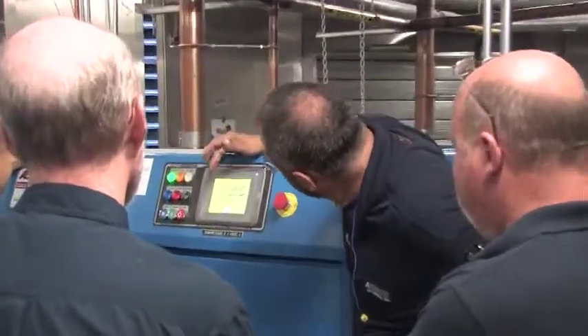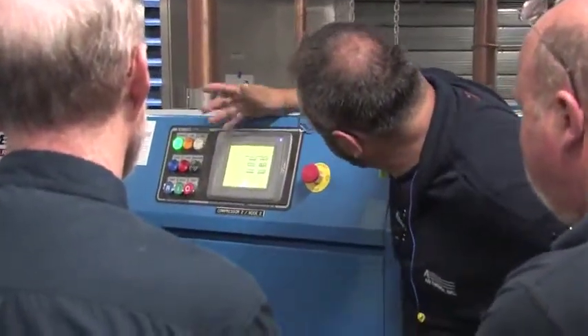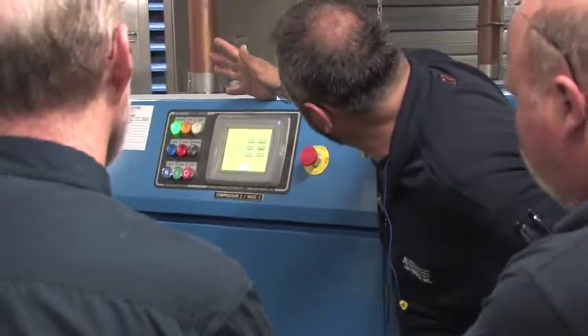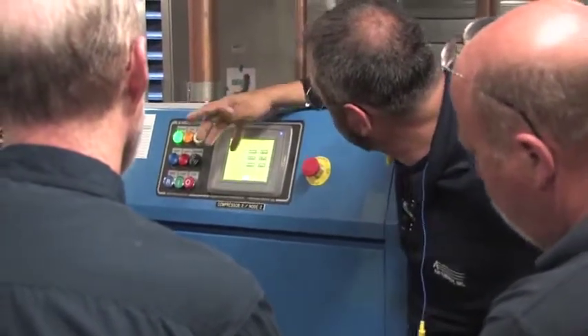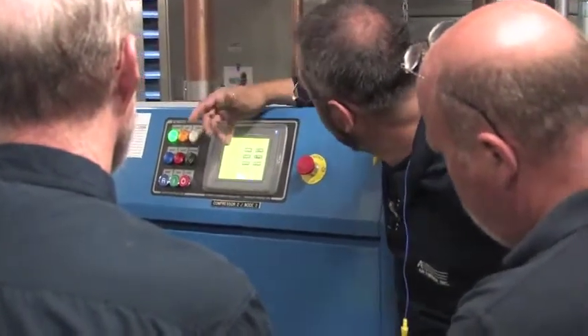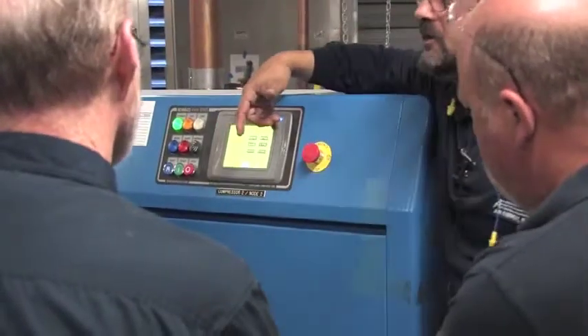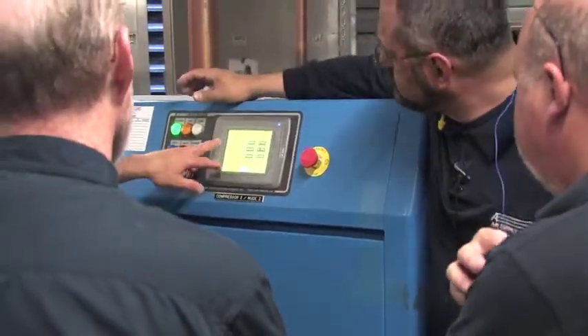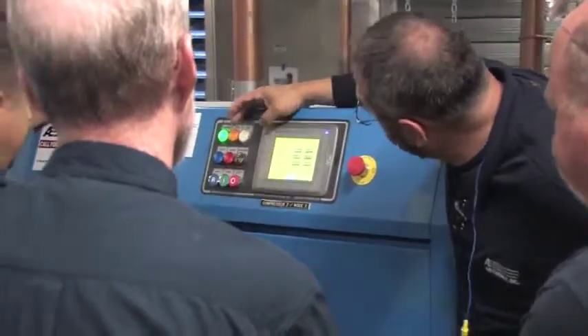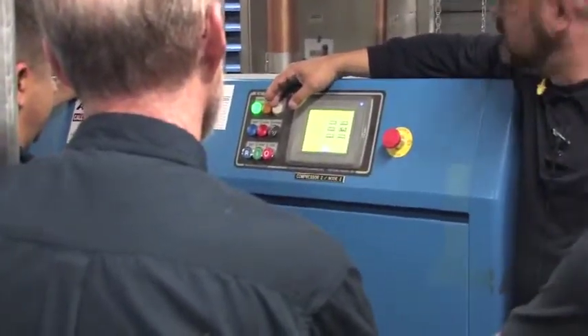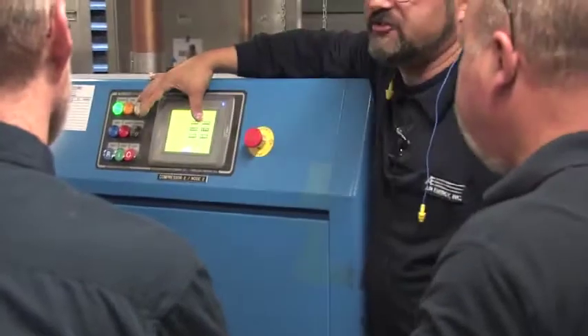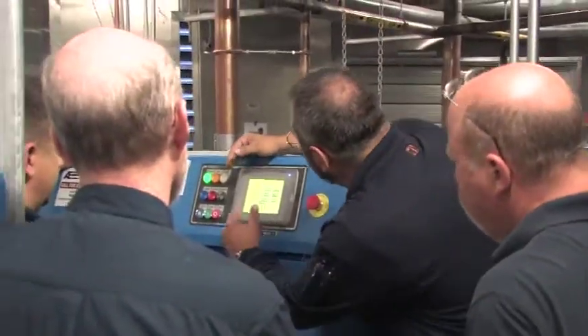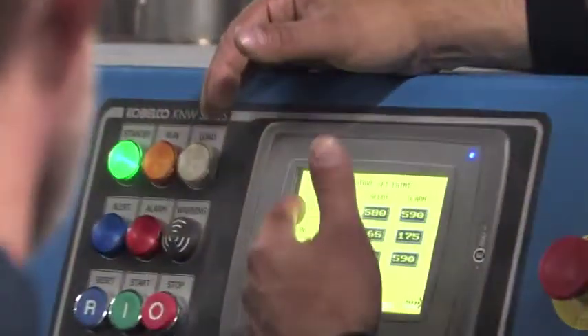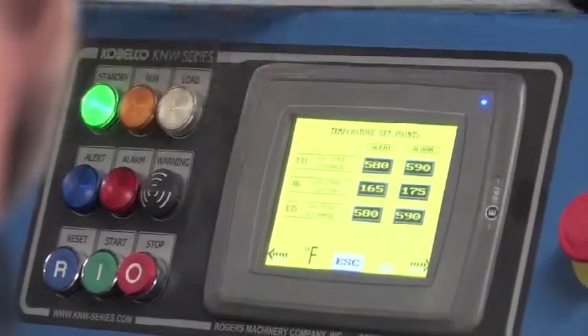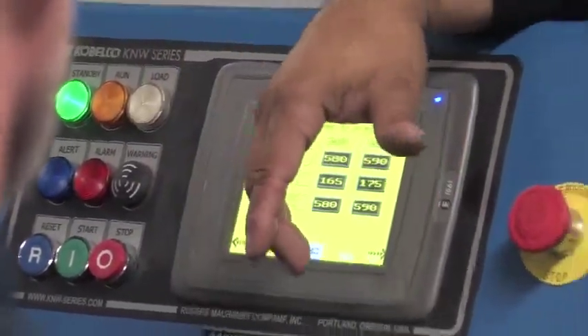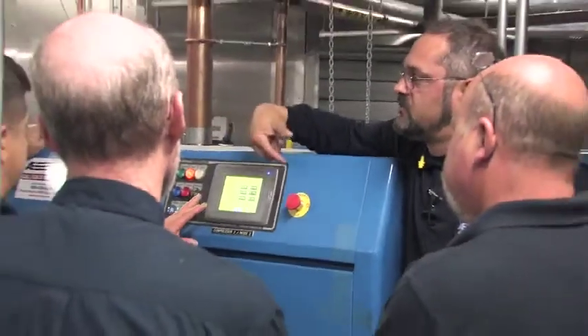Interesting. So you'll see the normal shutdowns and alerts, the same as they were in the older machines. First stage discharge, second stage suction, and you can see these are the alarm points and shutdown points. So this is also giving you your current temperature, and it's showing you what it actually is. The reason for this is obviously the way we test these. Drop that down to 128, we'll make that 128, and the alert light should go on. Gotcha. So that's how you can test them without ever running the machine and beating the hell out of it.